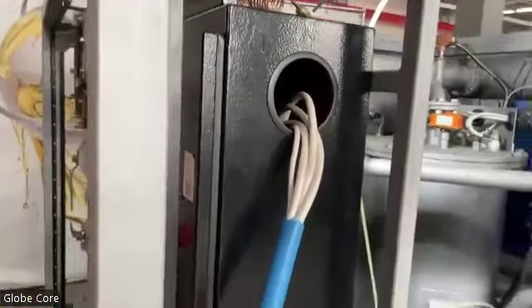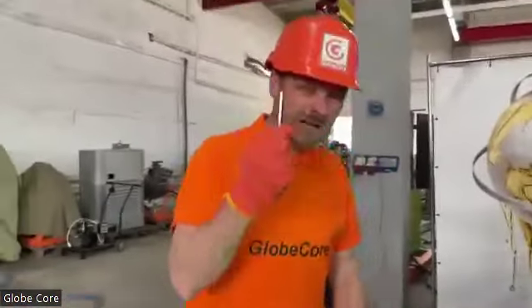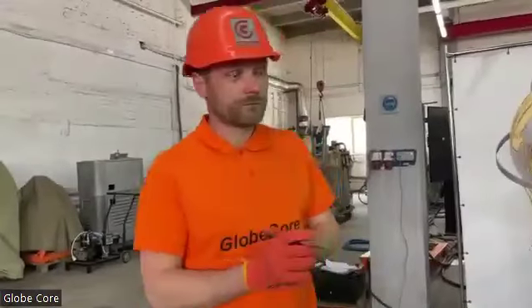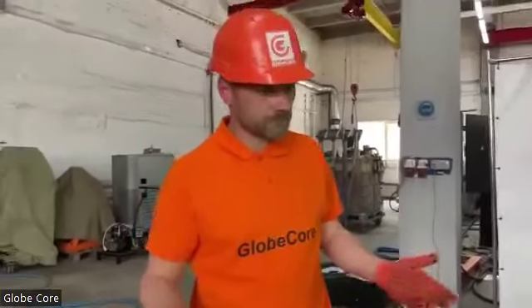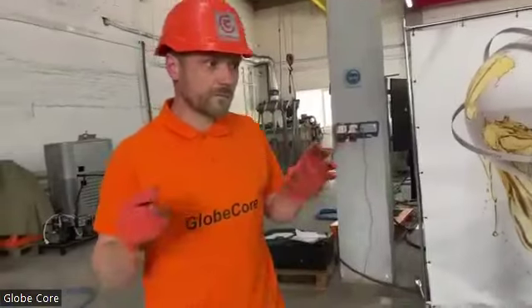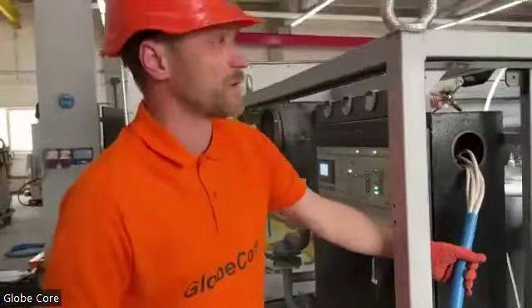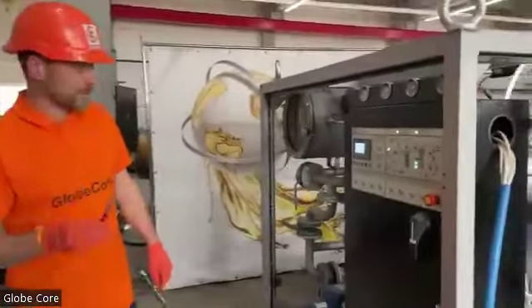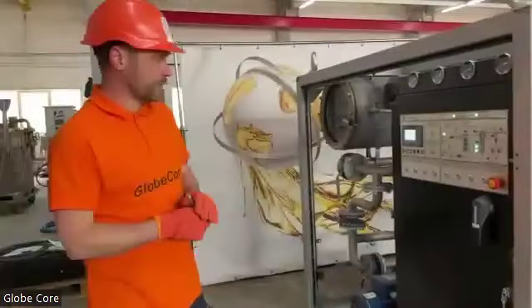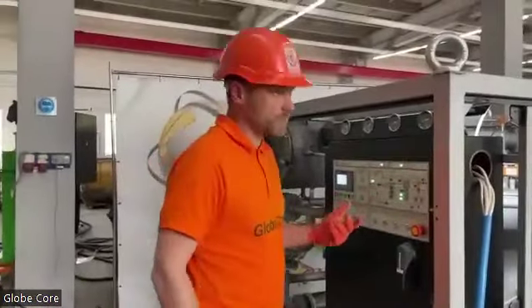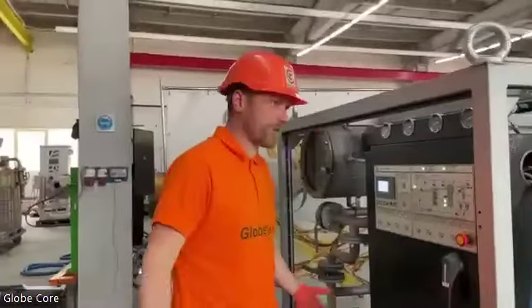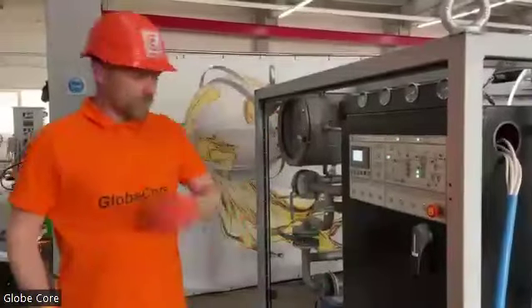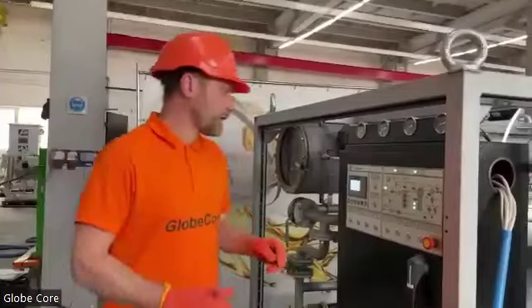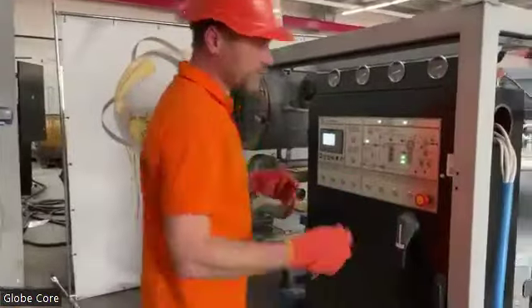Here I have the cable of 35 square millimeters, 4 wires of 35 square millimeters. And this is enough to start with one heating section only. So while commissioning, a 35 millimeters cable is enough to run with one heating section only. So with this one, you cannot run the unit on the full capacity. But sometimes while commissioning, it is okay to run with one heating stage only. You actually can change the heating to show the operation to the client.